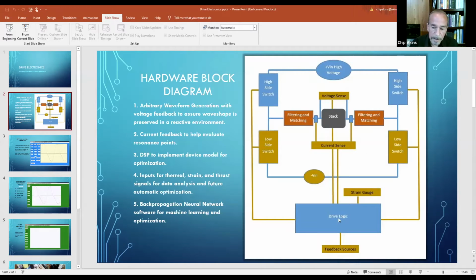There's drive logic, including a DSP and all the associated logic required, a bridge drive, a little bit of inductive filtering to get rid of the high frequency switching noises, and provide the drive to the stack. We have voltage sensing and current sensing on the device under test, and we also have strain gauge input and other feedback sources available in the electronics hardware, so we can take data from several different sources to help control the center frequency, the power output, and waveform, etc.